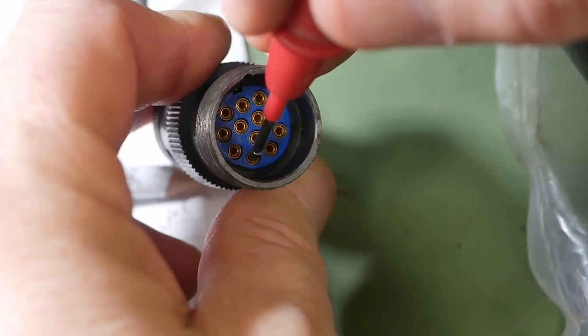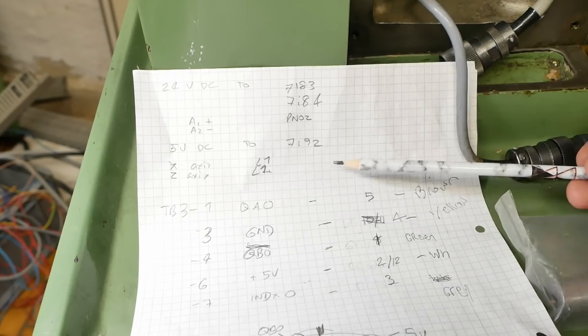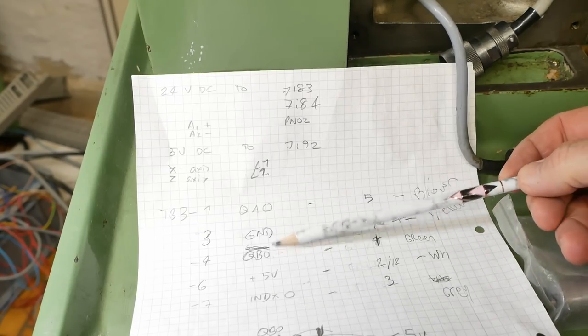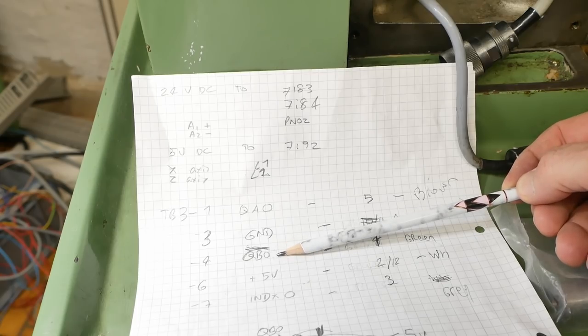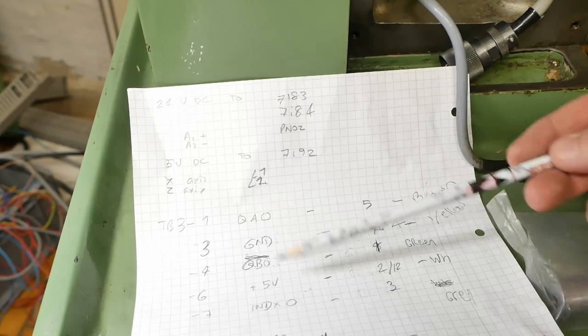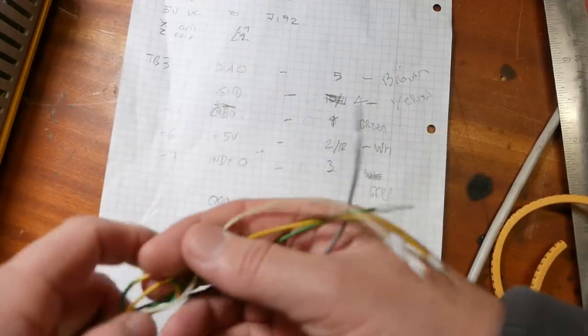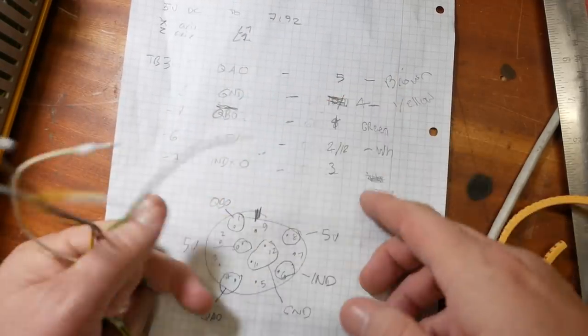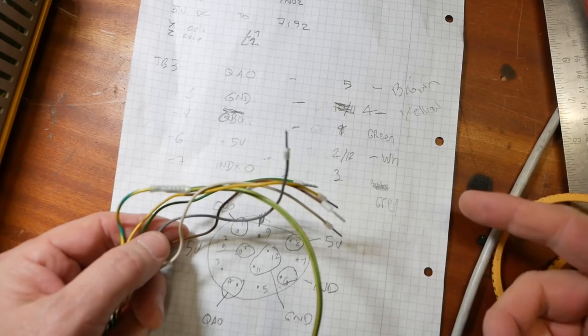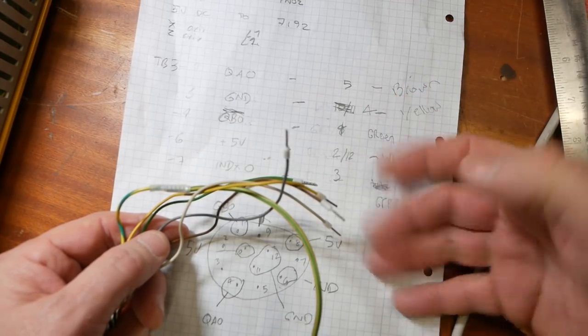Okay so it's pin 4. That's not great. Four out of the five signals I could find. Although this one's questionable because it's the inverse B channel and not the normal one. But the ground signal's not on a pin it should be on. Maybe they've changed their pinout in the last 40 years. Right so based on both wire colors and also the measured pinouts I can identify which is the encoder's positive, which is the negative and which are the three index.